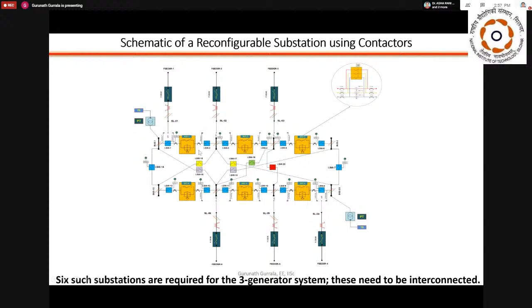So we need breakers, and each breaker will have two isolators on both sides for manual reopening. And then we also have what is called an earth switch in the system. You have to have an earth switch so that you can completely isolate the person. Before the switch is closed, no person can go and touch the systems. All these things have to be taken care of, and there is significant logic that you need to build so that all these work in a proper way, the way it works in the field.